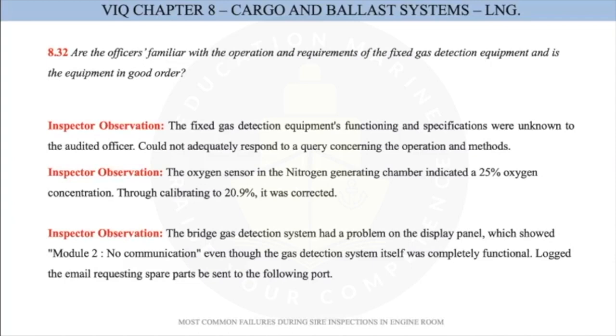Second one, the oxygen sensor in the nitrogen generator chamber indicates 25% oxygen concentration. Through calibration to 20.9, it was corrected. So the O2 sensor on the nitrogen generator was showing a wrong reading, and after calibration it was showing correctly. So that means that the calibration was not carried out as per schedule.